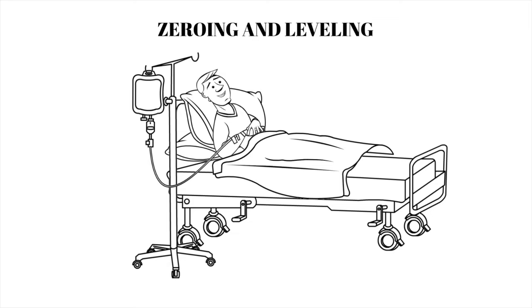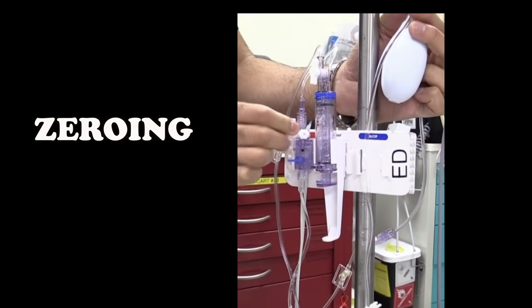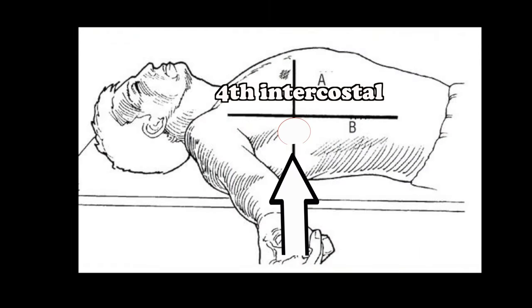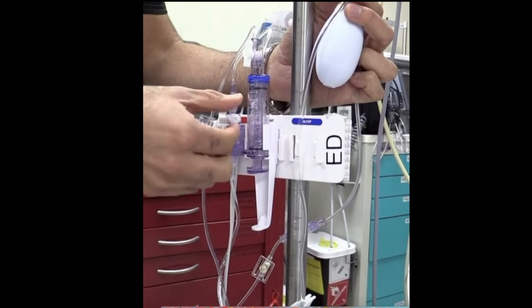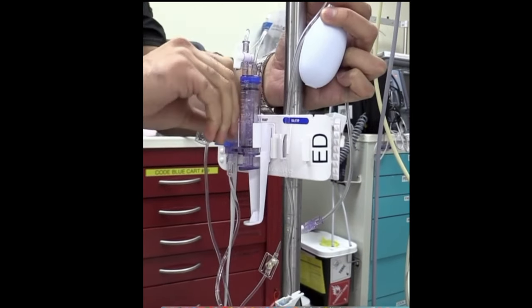Calibration of the system to atmospheric pressure, or zeroing, and determination of the phlebostatic axis for transducer height placement, or leveling, are required. Zeroing the transducer: turn the three-way stopcock open to air and close to the patient and the flush system.